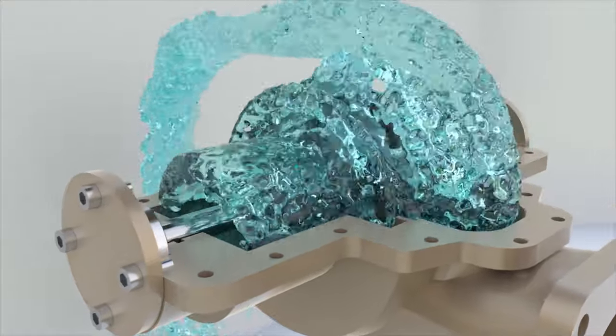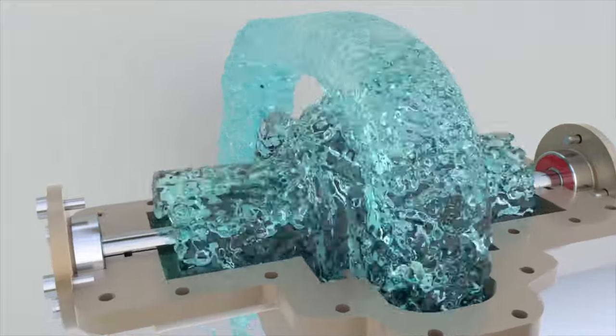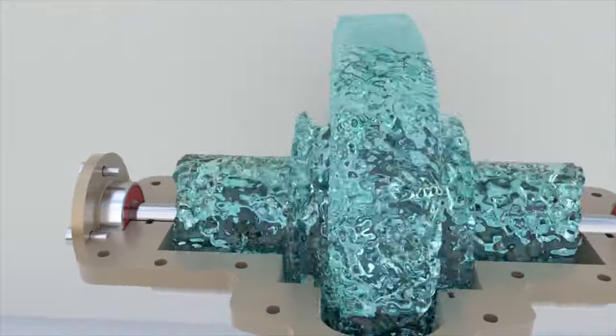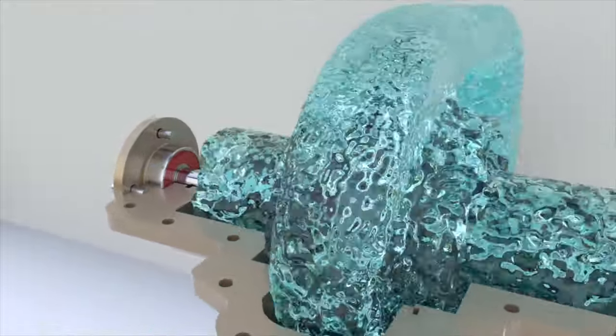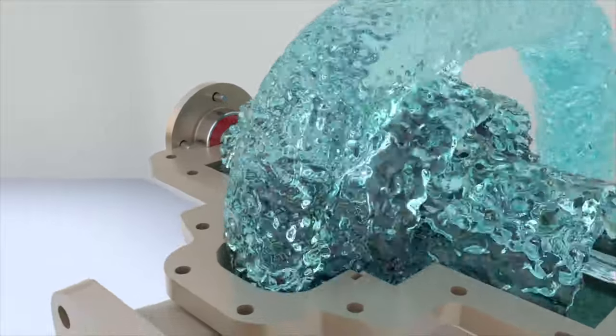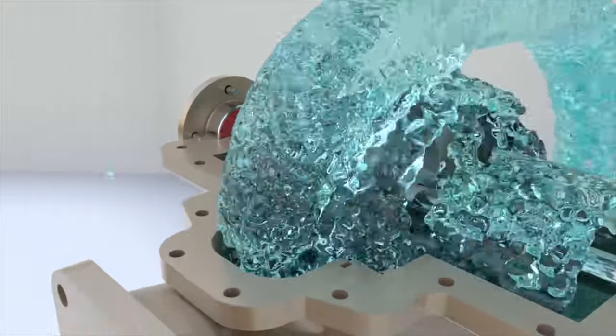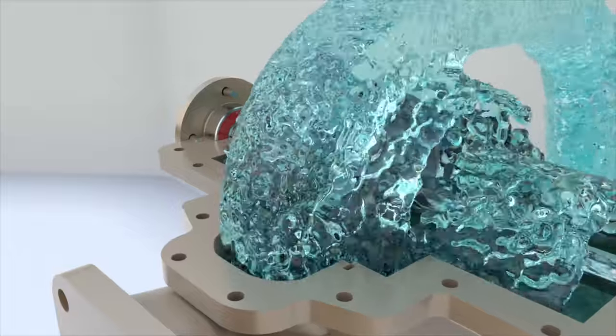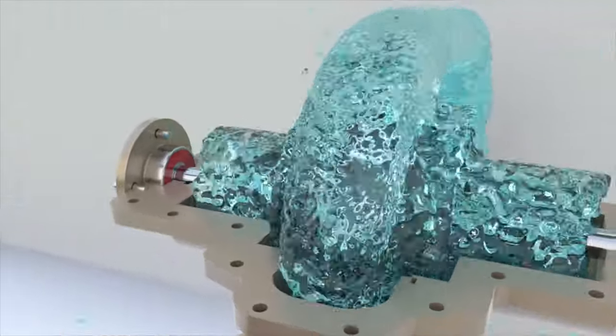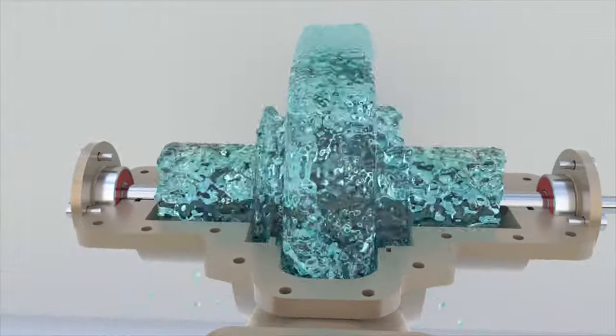A double suction impeller allows liquid to enter the impeller blades from both sides. Thus, we have two pumping units without significantly increasing the weight and dimensions of the pump. This scheme is relevant for pumps with high capacities because the pumping units are installed parallel.